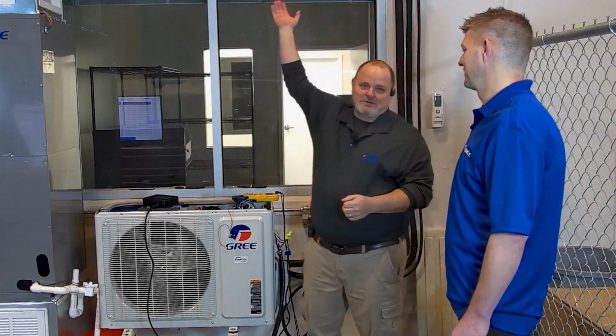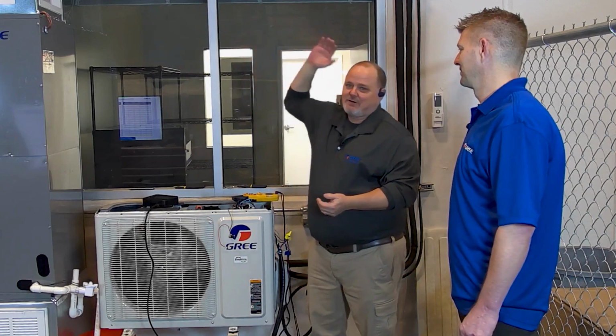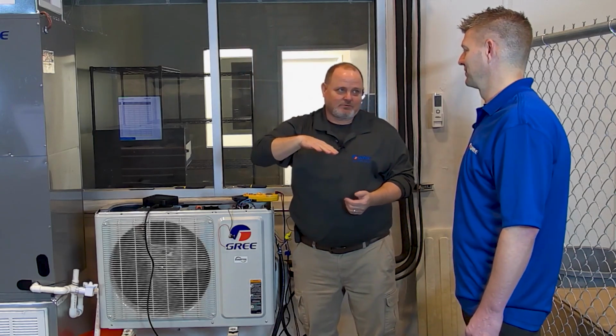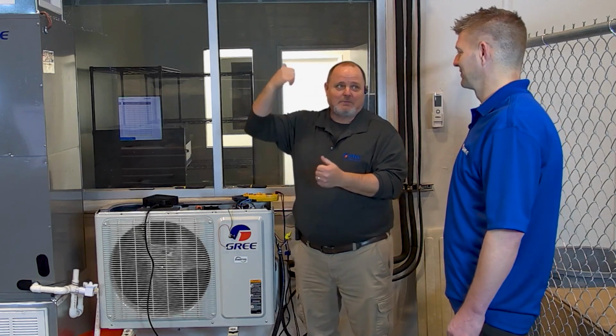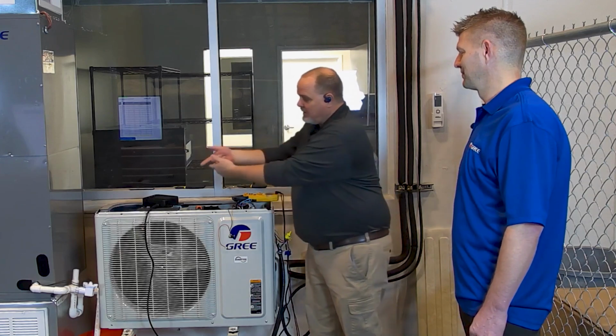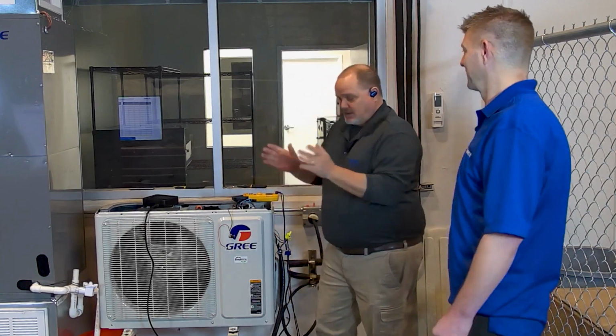Yep. Because it gives you all the information you need to know. Because if I've got my outdoor coil temperature in heating mode, and I convert that on a pressure temperature chart, I know what my suction pressure is, right? Yep. If I take my indoor coil temperature, which is now my condenser, and I convert that back to pressure on a pressure temperature chart, I know what my head pressure is. Yep. So I don't really have to have gauges hooked up to be able to get both head pressure and suction pressure with a service tool. That's my point. Saves a lot of time.